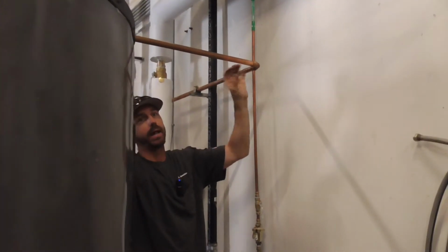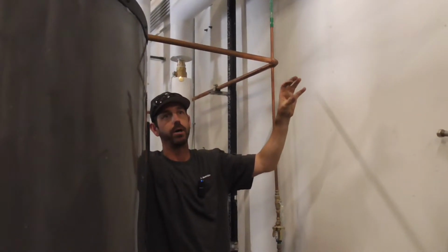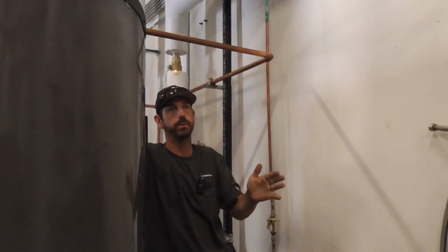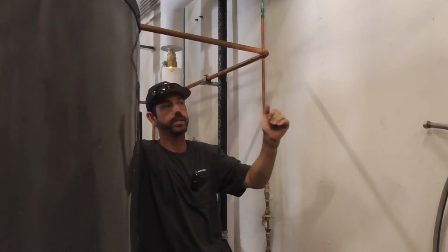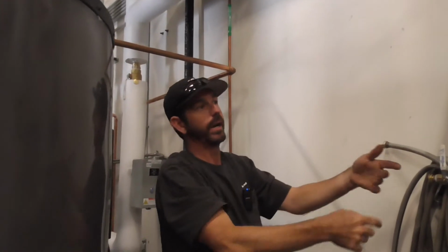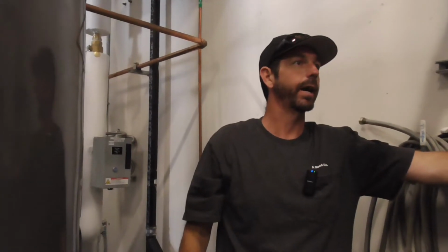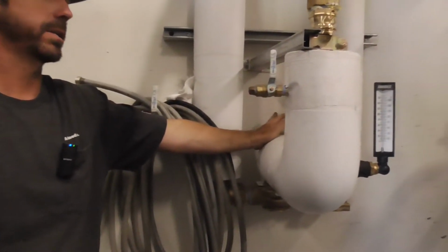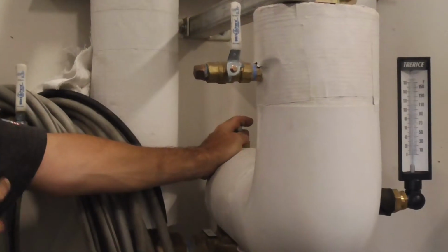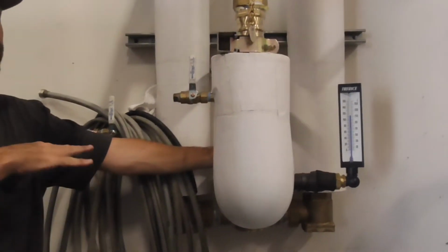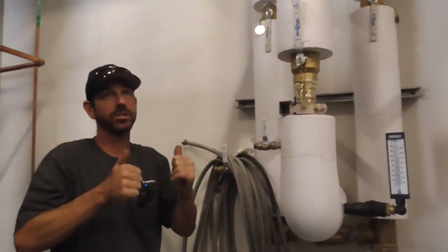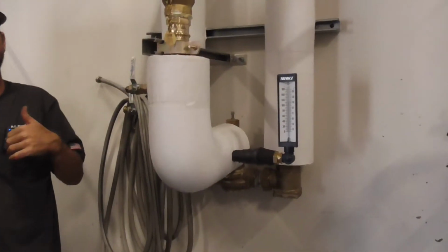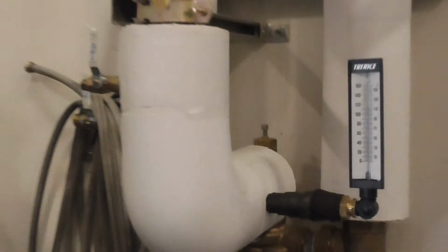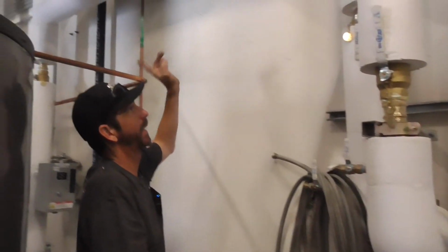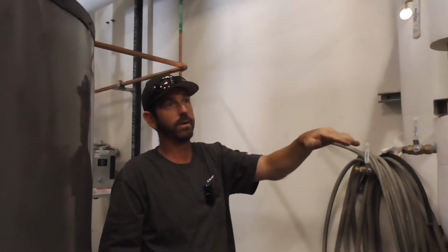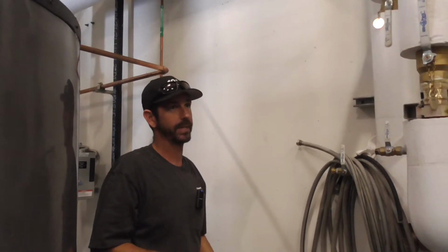Right now, the system's balanced for that 118 under no loads. Because again, the circ pump is only for when nobody's using water. If somebody's using water out of a fixture, you're mixing your hot and your cold together, and that's where this setting comes into play, okay? Because this adjustment is only made with flow. Once you've set it, then with no flow, and when I say no flow, it's no fixtures open in the building, you're going to have flow by the pump. You have to make sure the pump's running. Then you would fine tune, like I said, the 2 balance valves to make sure you're always maintaining that 118, okay? Does that make sense?